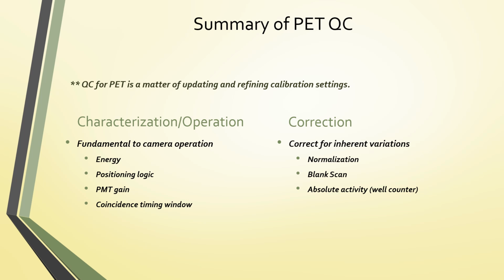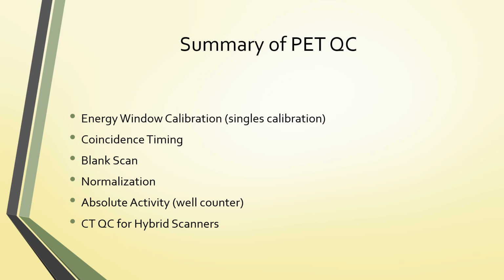Now, when we're performing QC for corrections, we want to correct for inherent variations that occur. So this would be your normalization and your blank scan, and then the absolute activity, also known as the well counter calibration. So the summary of the QC: the energy window calibration, where we're looking at singles, coincidence timing. You want to make sure the coincidence timing window is acceptable for use, performance of a blank scan, normalization, absolute activity with the well counter, and then if it is a PET-CT system, you also have to do the CT QC for hybrid scanners.